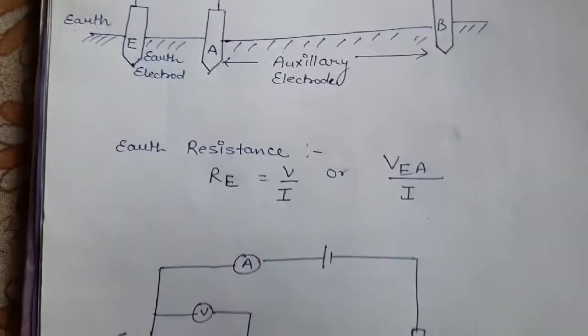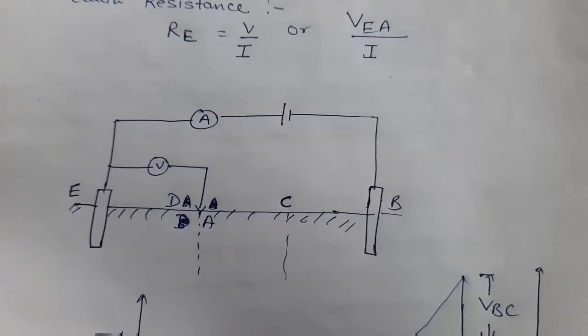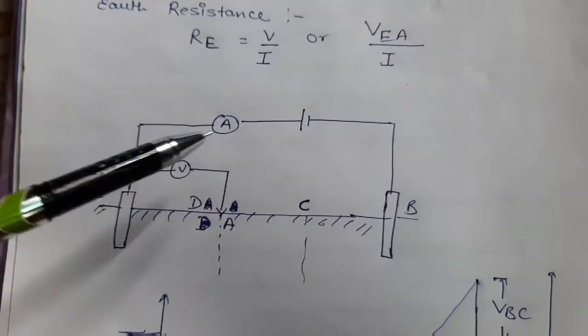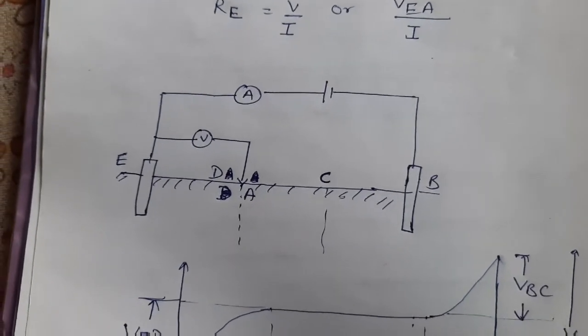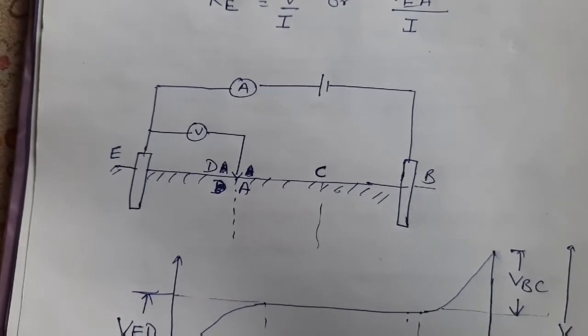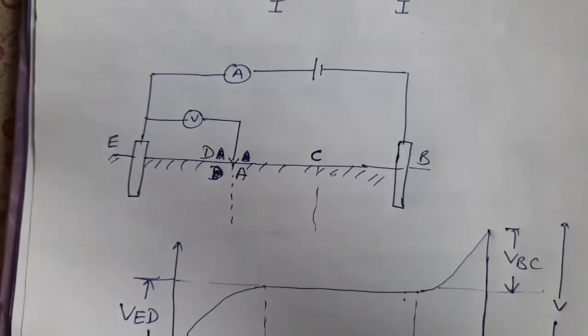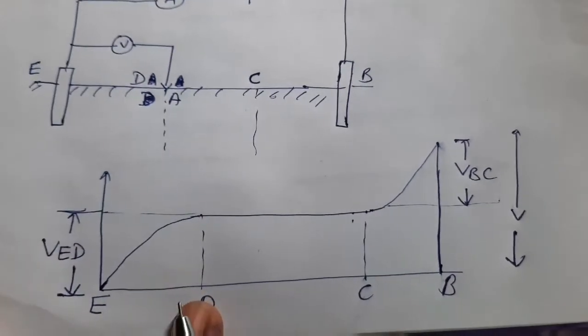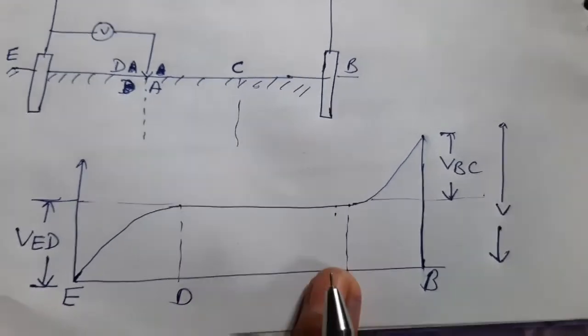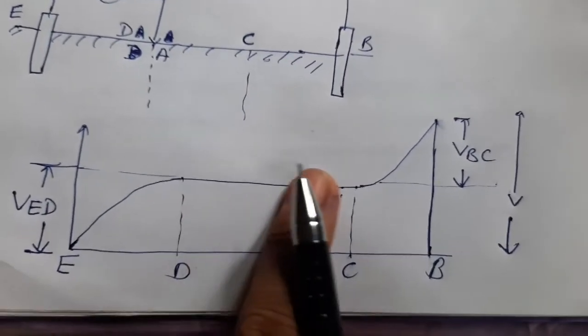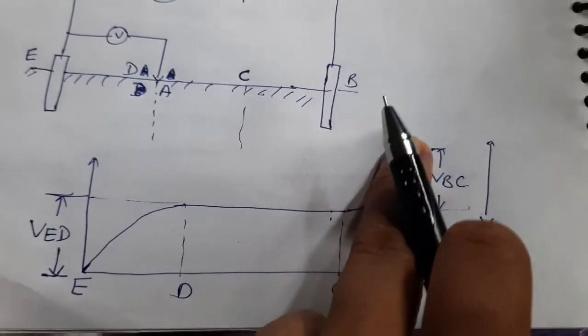Let's see this diagram. The auxiliary electrode position is varied, shown by a dotted line, while the other two electrodes are fixed. Initially when going from E to D, the voltage rises. Between D and C the voltage is constant, and again between C and B the voltage rises.